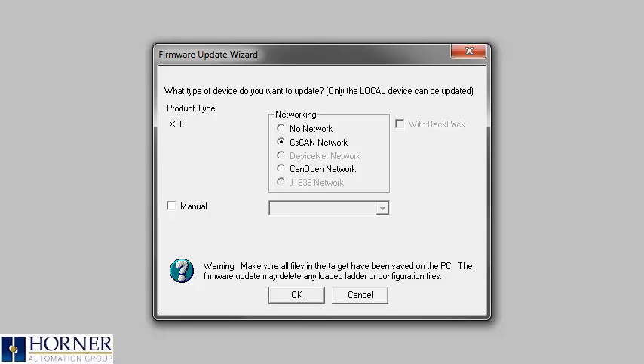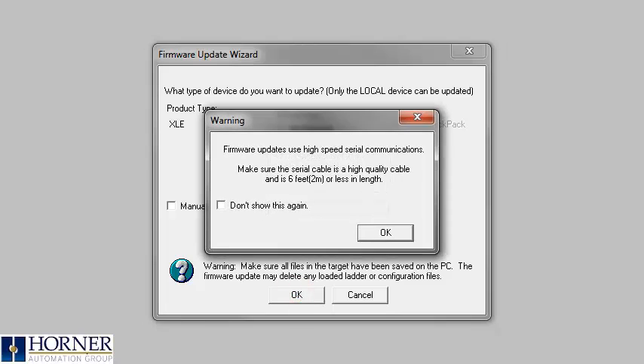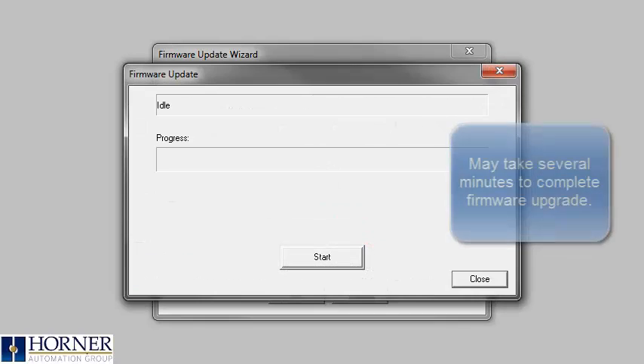Make sure that you have a copy of your program available because this will clear the memory of the controller. Select OK a couple of times and then start to begin the firmware update. Be sure to follow all instructions. Now this can take up to several minutes to complete.